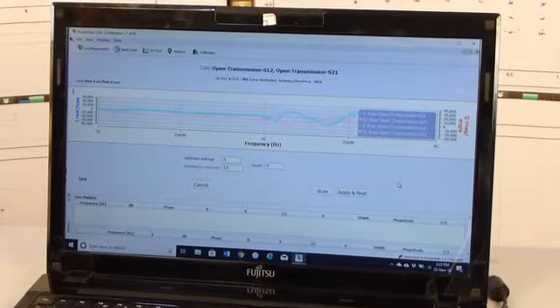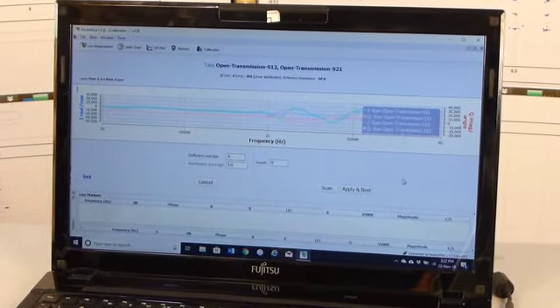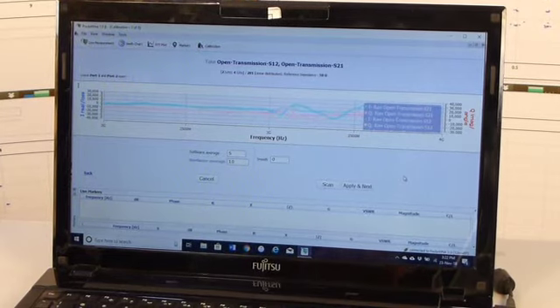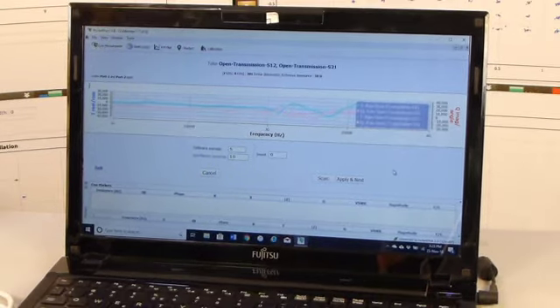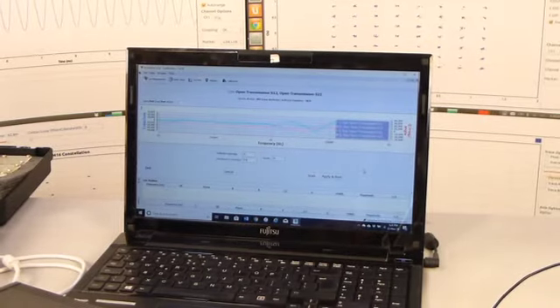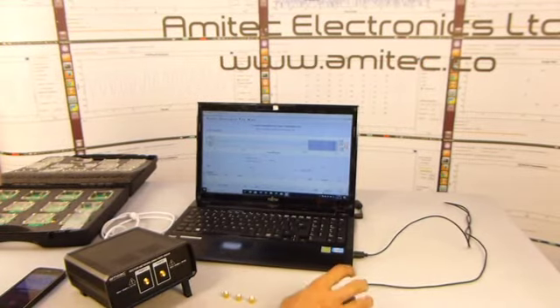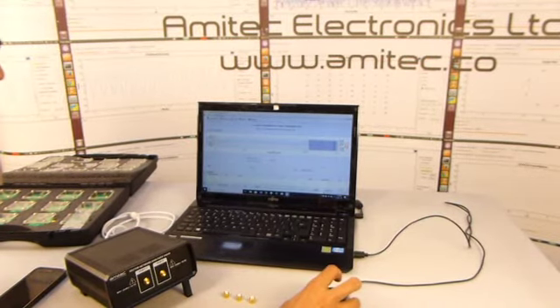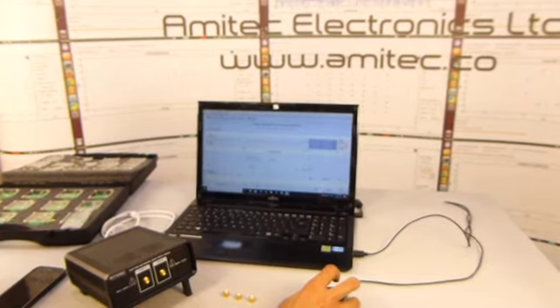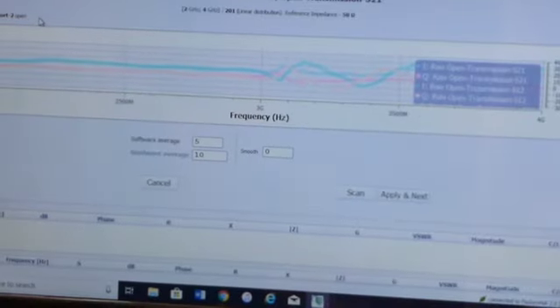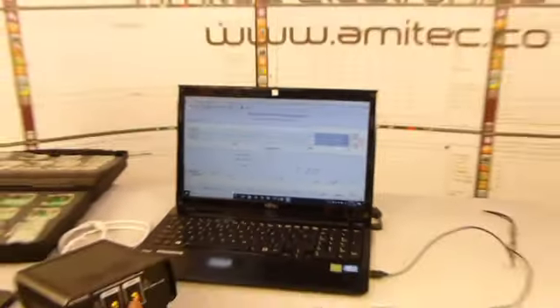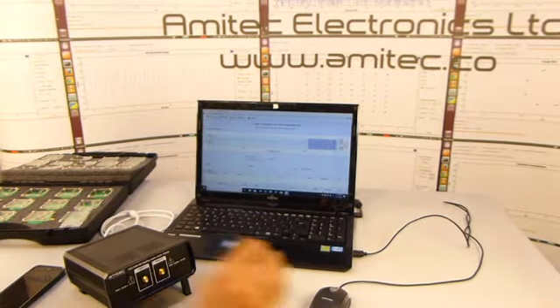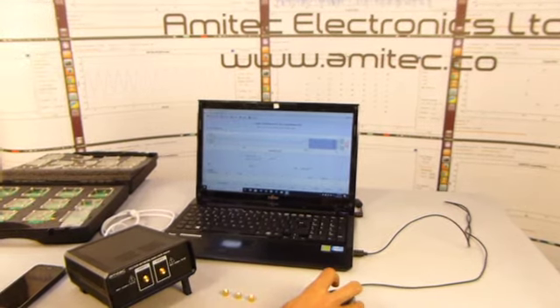through. We connected the short at port 1 and 2. After that we connected load at port 1, then at port 2, then open at port 1 and port 2, and as you can see in the software it says calibration 7 of 8. The last step was leave port 1 and 2 open. Now here 1 and 2 open means do not connect any short, open or load on these two ports and leave them as they are. Now after scanning, we will press apply and next.